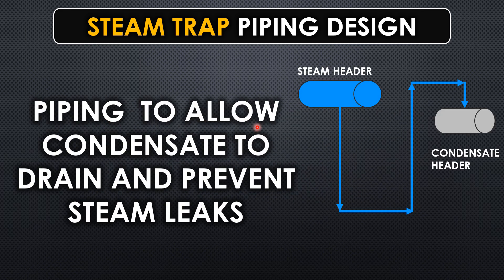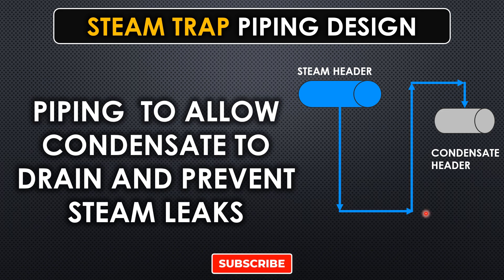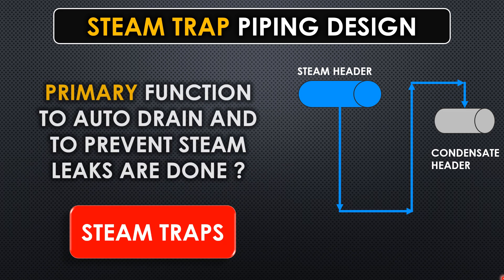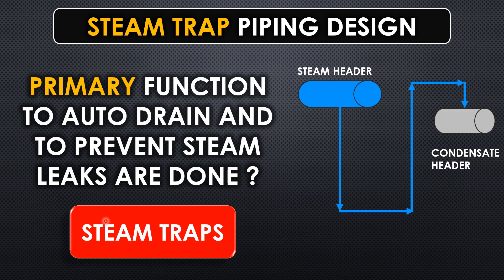The steam trap piping is designed to allow the condensate to drain and to prevent steam leaks — it does both functions. One is to drain the condensate and another is to prevent steam leaks. But it is not possible for piping alone to perform two different functions at the same time. That's why a component called the steam trap is used, whose primary function is to auto-drain and to prevent steam leaks.